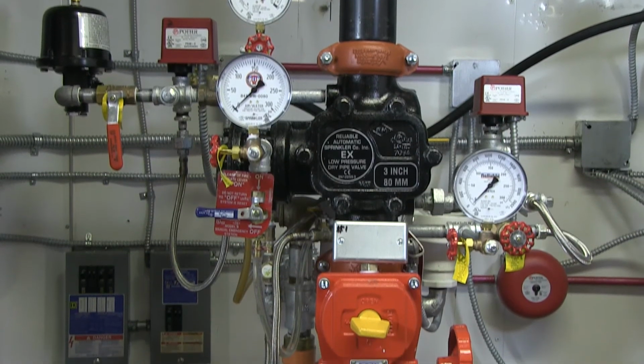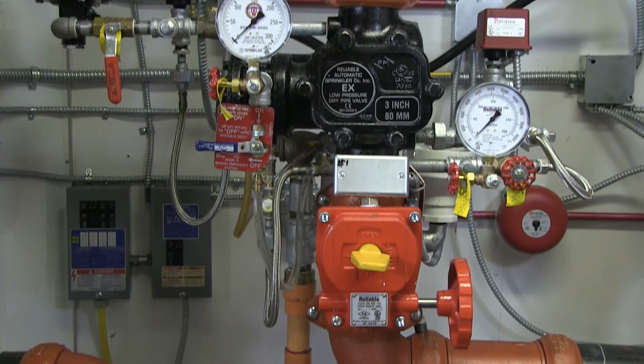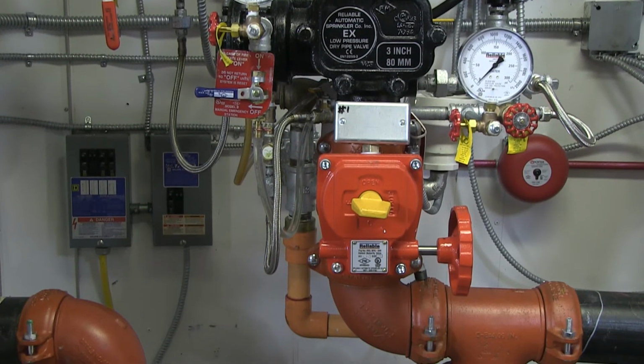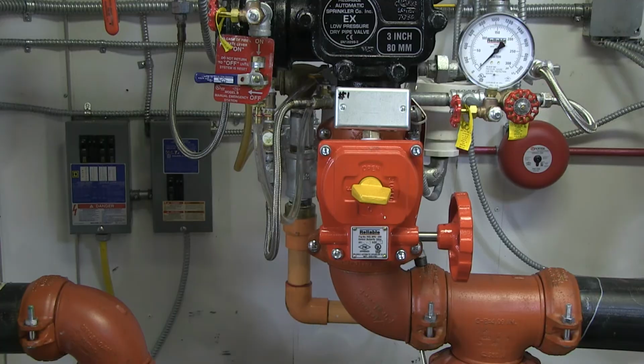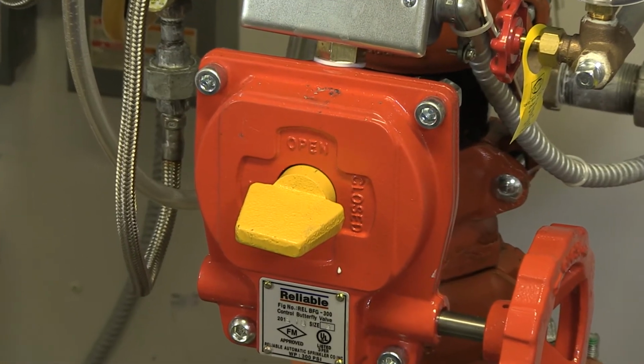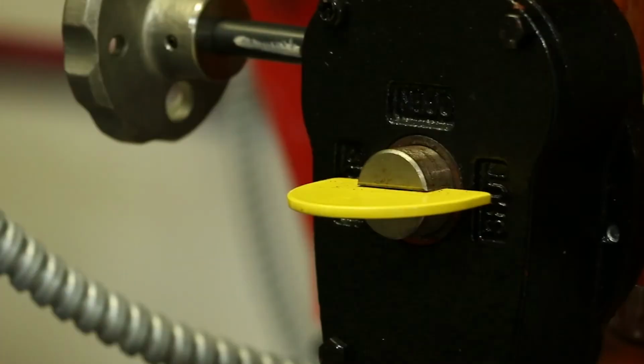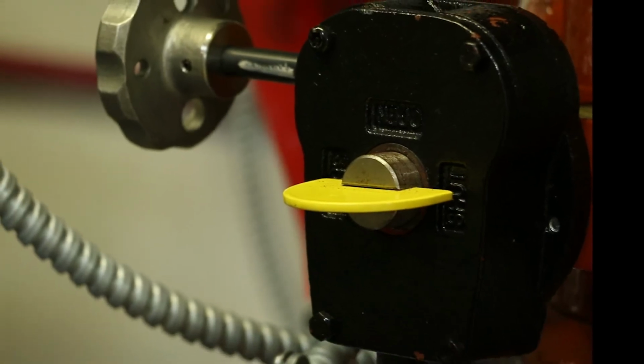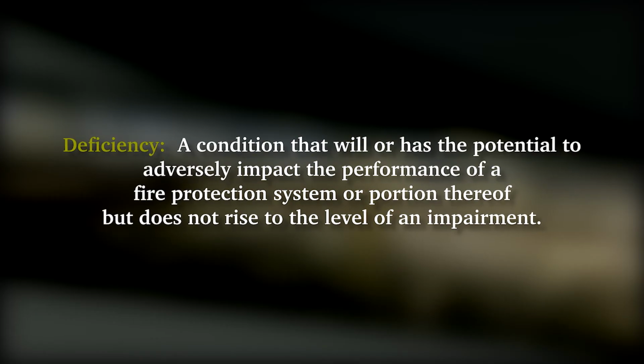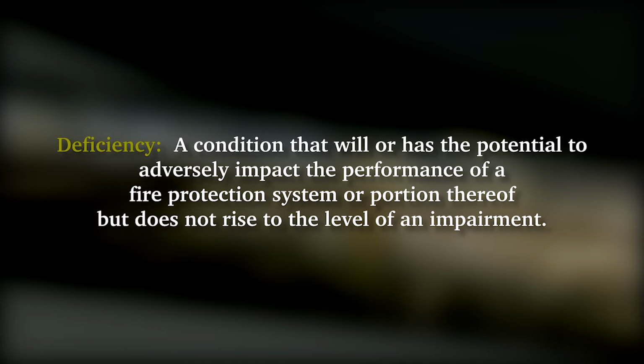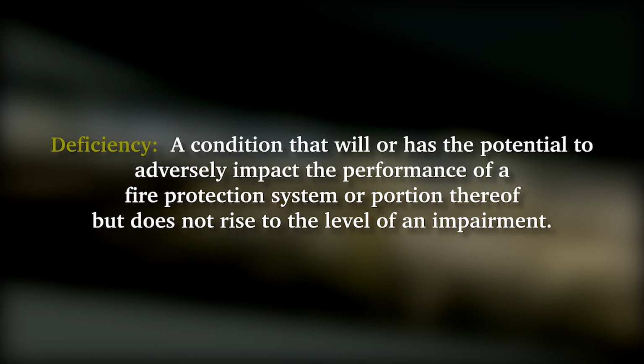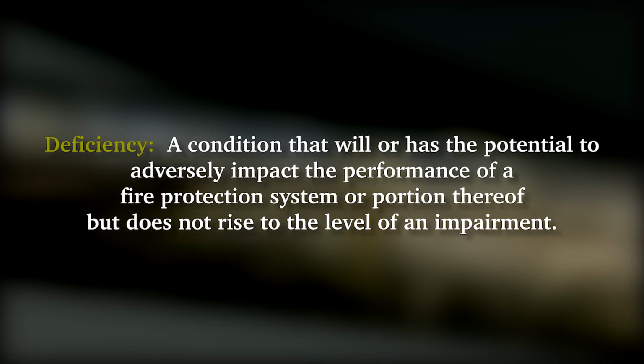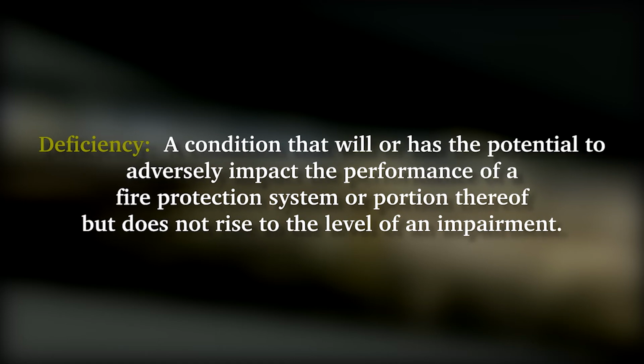According to the National Fire Protection Association, when fire sprinklers fail to operate, the cause was most often due to the system being shut off, typically a valve that was manually closed in the course of routine inspection and maintenance, but had not been reopened. A deficiency is defined as a condition that will or has the potential to adversely impact the performance of a fire protection system or portion thereof, but does not rise to the level of an impairment.